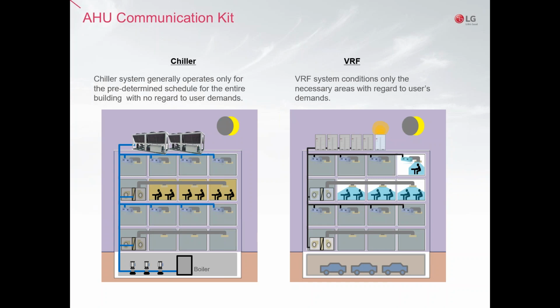In the case of the boilers, I've seen some retrofits where the air handler units are old, but you only replace the coils. Sometimes you even leave the hydronic coils if they still work, but you can cut a lot of the capacity of the boilers, and you can liberate all the space in the basement as well. And in this case, in the drawing on the right, you only have some offices working, and because of the way the VRF works, you can have a very limited operation of the condensers through the day, through the night.